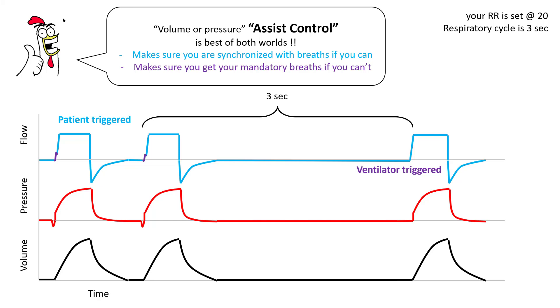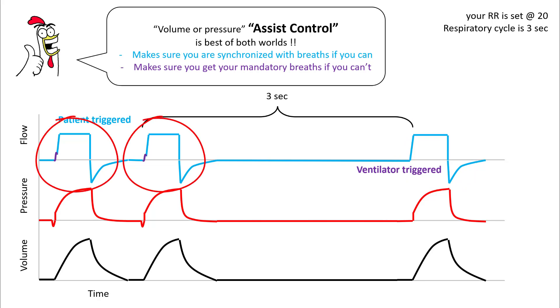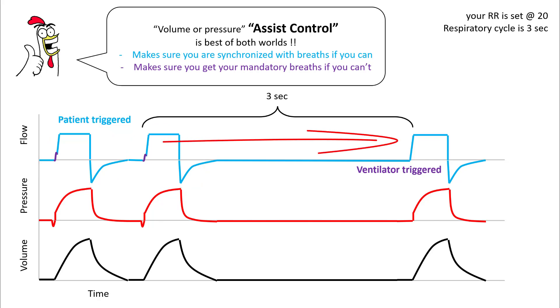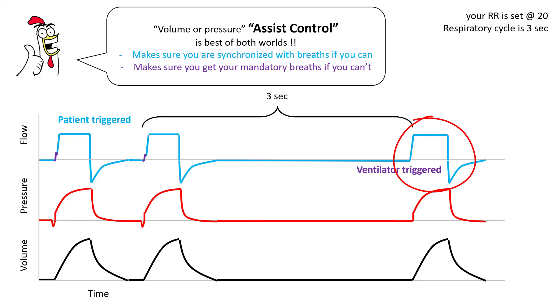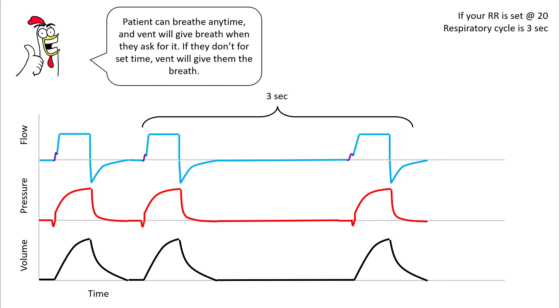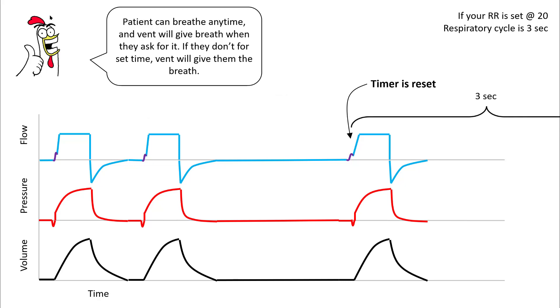Since patient-triggered and ventilator-triggered breaths each have their own advantages and disadvantages, you can combine both triggers in what we call assist control. In assist control, patient-triggered breaths are prioritized — whenever the patient wants to breathe, the machine gives the breath. If the patient cannot generate a breath, they get mandatory breaths from the vent trigger. For example, if the patient was triggering initially and then did not trigger for 3 seconds, the vent triggered it since the respiratory rate was set at 20. If the patient wants to breathe before 3 seconds, they are allowed to do so and that resets the timer. Every time the patient triggers a breath, a timer starts, and if the patient does not breathe within that time, the ventilator will trigger the breath.